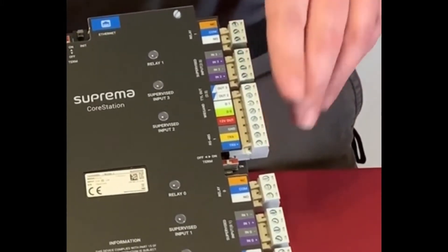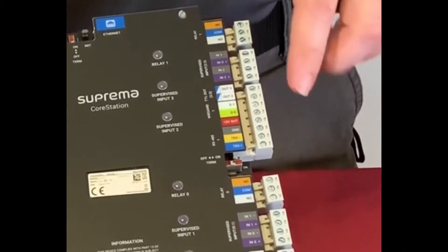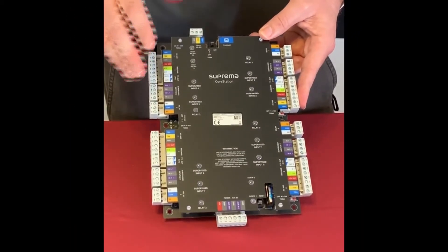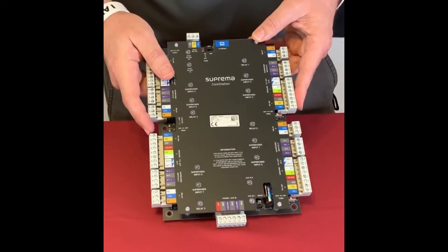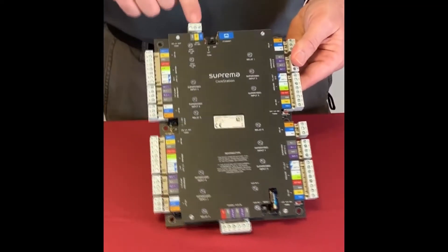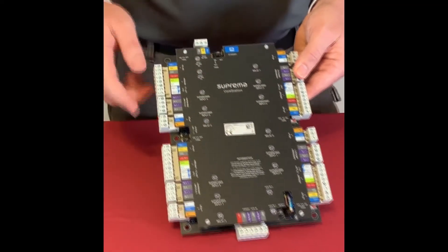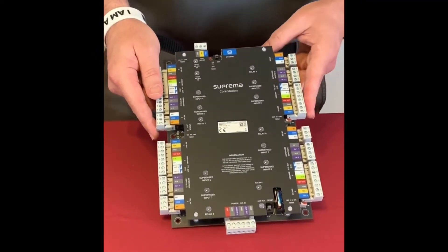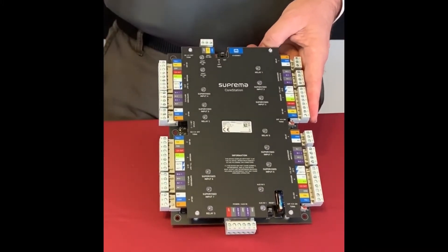You can daisy chain up to 31 devices off one RS-485 port, and the core station supports up to 64 devices total. We actually have four RS-485 ports — one in each door port, plus a host port at the top. So you can daisy chain up to five different legs, with up to 31 devices per leg and 64 devices total.